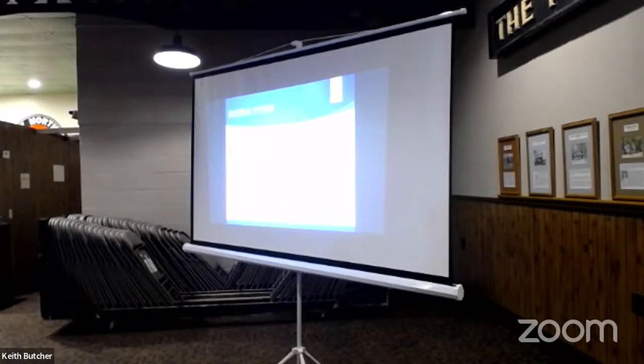Let's talk a little bit about generation at the power plant. You've got a mix of 5 diesel-fired generators there, and the age really ranges. The 4 of the oldest units, you've got the Fairbanks Morse, the Enterprise, the Superior, and another Enterprise at engine number 6. And then you have the newest at engine number 7, which is your Caterpillar unit that was put in 2002. It's also the largest unit. Total generating capacity is approximately 12.1 megawatts, or 12,190 kilowatts.